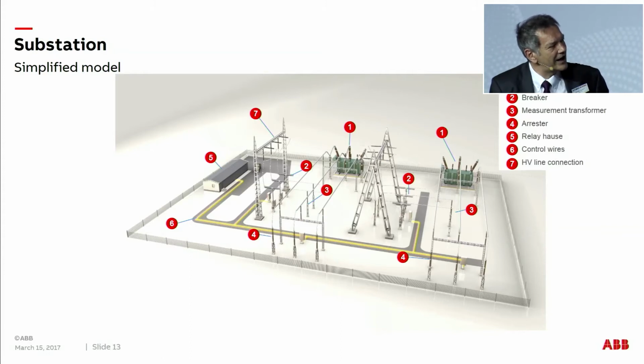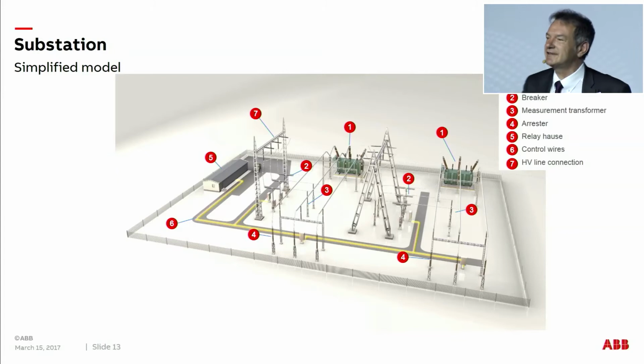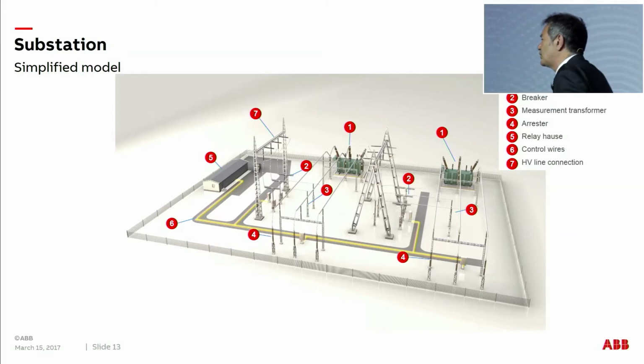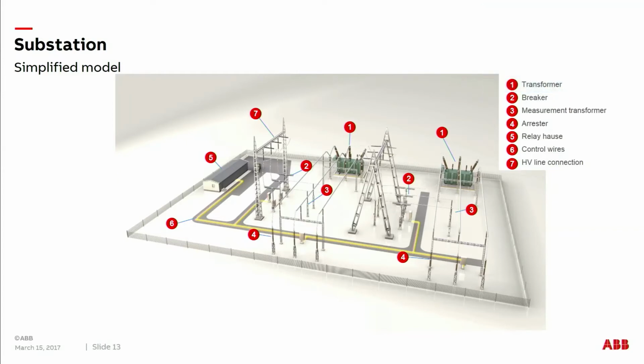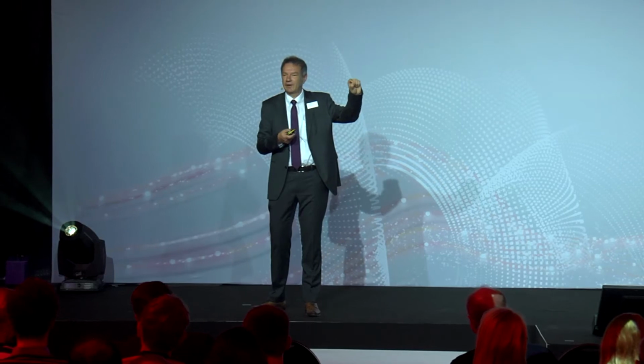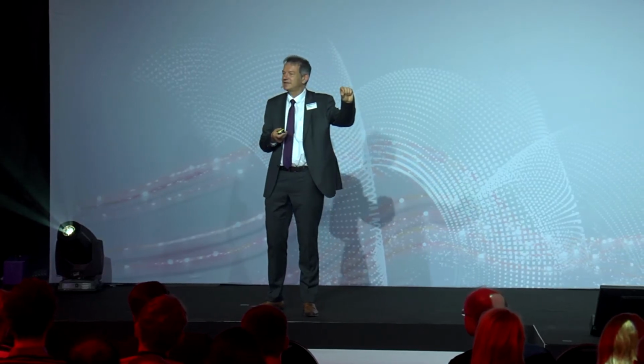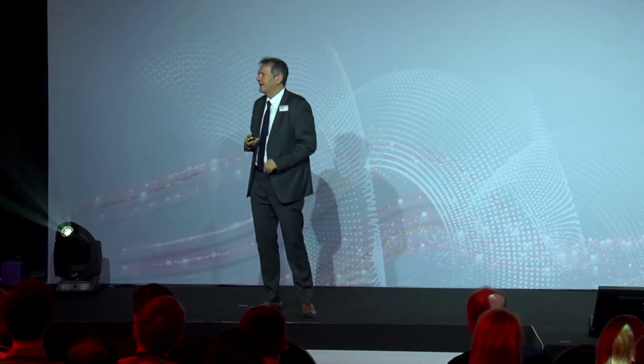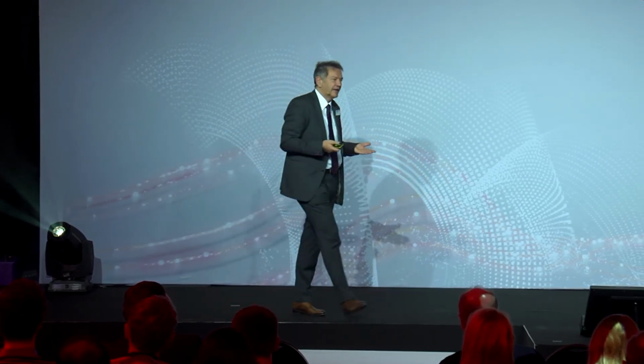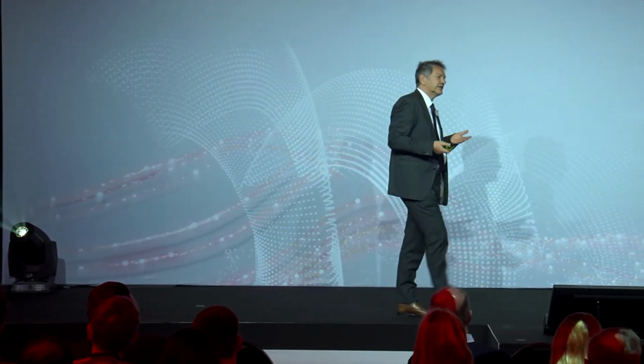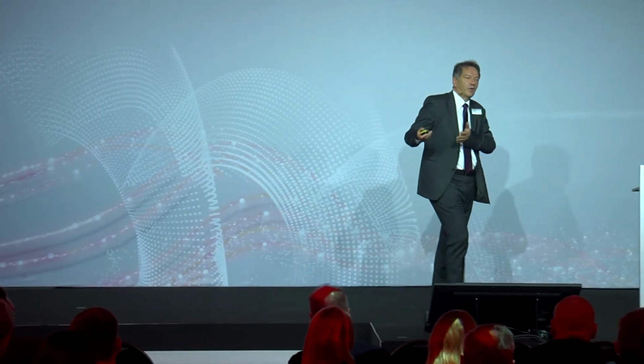Today, in conventional technology, this yellow stripe is still thousands of point-to-point wires. In such a substation you can have more than 10,000 individual wires connecting, for example, a tripping output of a protection device to a breaker. A lot of things have to be redundant, and you can imagine how difficult the engineering of such a substation is with all these things.